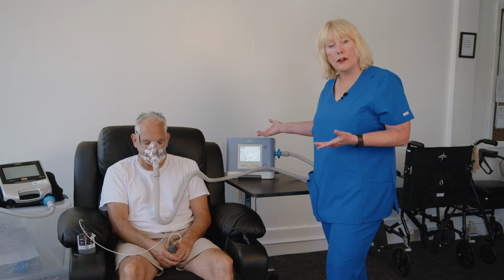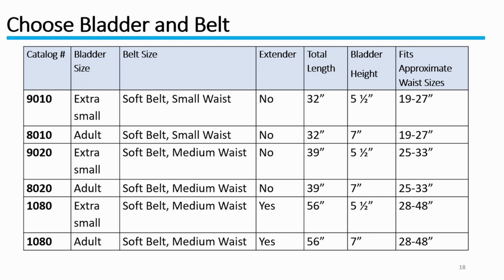Choose the appropriate bladder and belt for the patient. There are 2 sizes of bladder, the adult bladder and the extra small bladder. And there are 2 sizes of belt, the adult belt and the extra small belt. There is also an optional belt extender, which can be used to lengthen the adult belt. Usually, when using a large bladder, the adult belt is used, but not always. There may be some situations where the large bladder is used with the small belt.